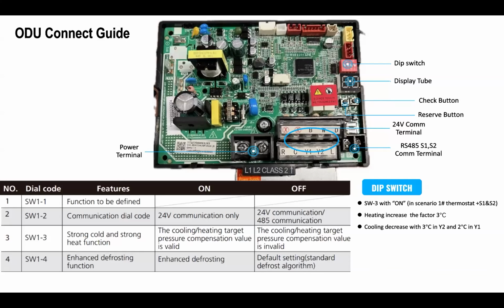Now, Eric, since we're going to be having an air handler, or if it's for an indoor unit, there's really no circumstance we should be required to run 24 volt control to our outdoor unit. It should always be able to be two-wire communication. Right. Even if you're going to use a 24 volt thermostat, we always want S1, S2 communication in the indoor and the outdoor. Yes, which is what we always want to recommend. We want to avoid 24-volt wiring to our outdoor unit in every situation possible.